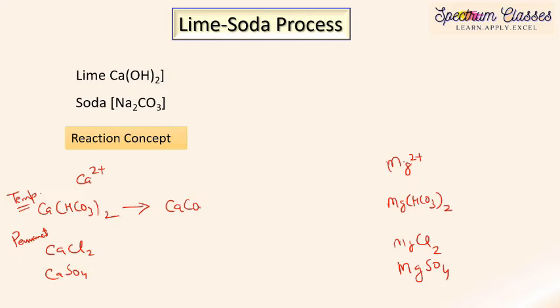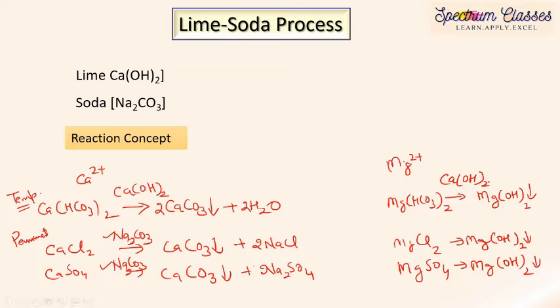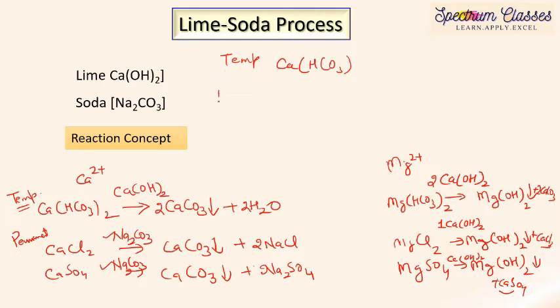The main objective of the lime soda process is to produce calcium carbonate (CaCO₃), which is insoluble, and magnesium hydroxide Mg(OH)₂, which is also highly insoluble and settles at the bottom. From calcium salts, we produce CaCO₃; from magnesium salts, we produce Mg(OH)₂ by reacting with Ca(OH)₂, which provides the hydroxyl groups needed.